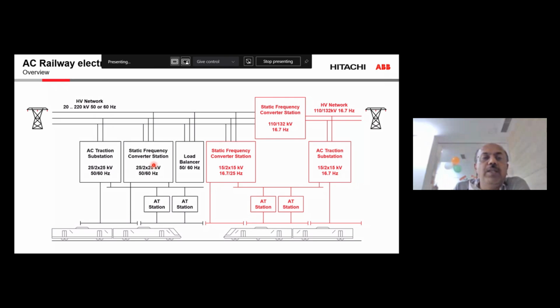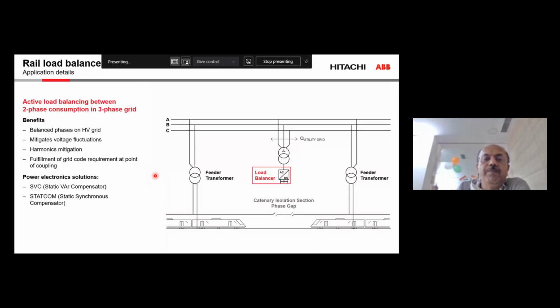The static frequency converter is another product which is extensively used in Europe, Australia and other countries, and it can adjust to any difference in frequency between the catenary and the supply frequency. Of course, that may not be a big criterion in India because the same frequency network is available all across. What is very important to notice here is that this static frequency converter not only balances the electrical parameters on the three-phase side, it will also enable the balancing of the entire corridor where this catenary network is connected through this particular static frequency converter.